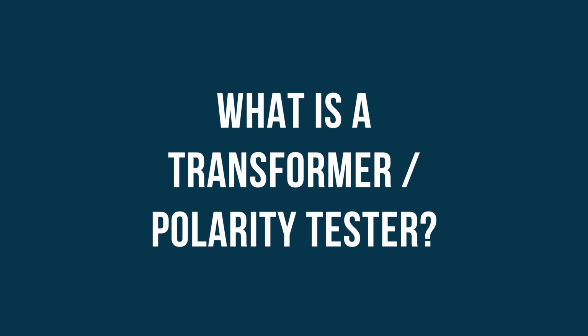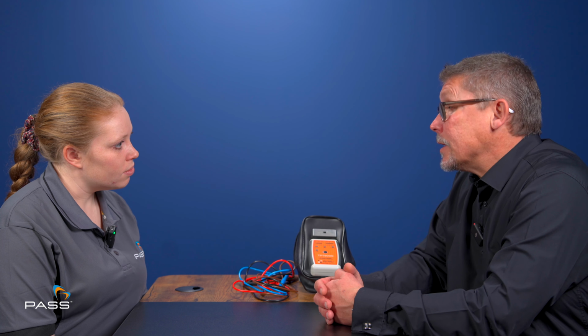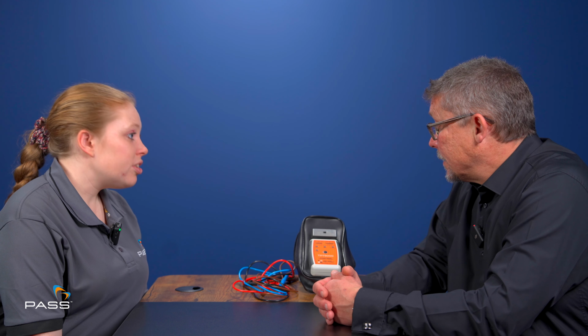Before we start talking about the TPT 9000 specifically, could you give us a quick overview of what transformer polarity testers are? So effectively, when you have a system, you'll have both VTs, voltage transformers, and CTs, current transformers, and they're directional. If you had two facing one way and one facing the other, that would cause a problem when monitoring a system. The VTs and CTs are invariably part of the protection, so they're normally linked to your relays and feed back through the relays to the circuit breaker, operating as a protective system to look after your plant.